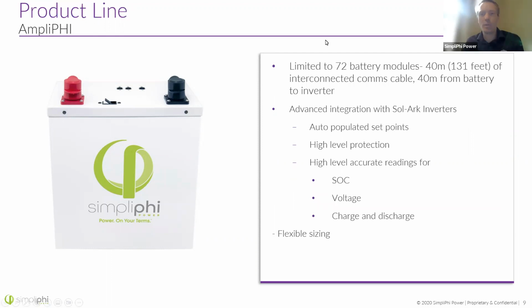Limited to 72 of these batteries, so this is highly scalable. We've got a 3.8 kilowatt hour battery, that's your building block, but you can do up to 72 battery modules in parallel. The limitation here is really based on the communication system, which can handle up to about 72 batteries in total, limited by the length of the Cat5 cable connecting the communication systems.